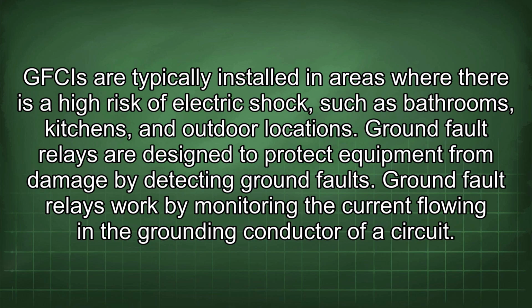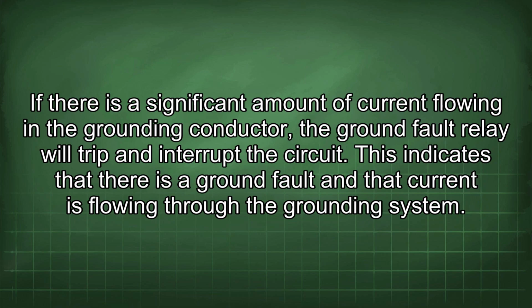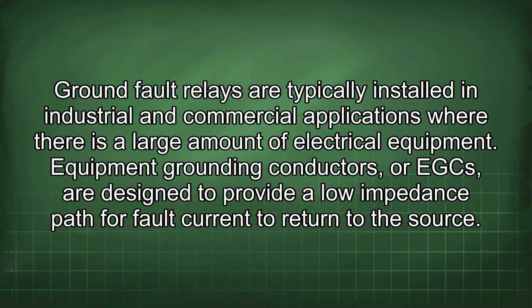and outdoor locations. Ground fault relays are designed to protect equipment from damage by detecting ground faults. Ground fault relays work by monitoring the current flowing in the grounding conductor of a circuit. If there is a significant amount of current flowing in the grounding conductor, the ground fault relay will trip and interrupt the circuit. This indicates that there is a ground fault and that current is flowing through the grounding system. Ground fault relays are typically installed in industrial and commercial applications where there is a large amount of electrical equipment.